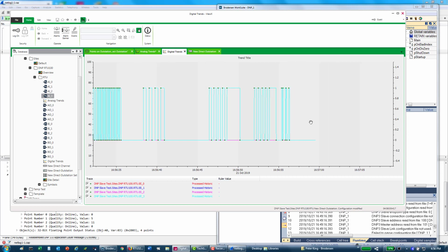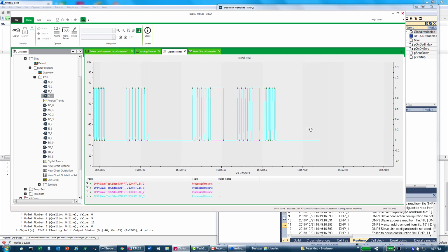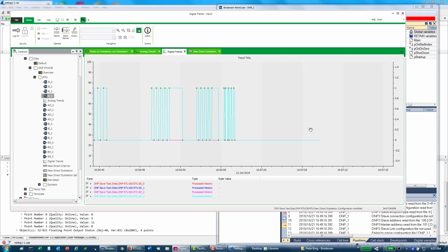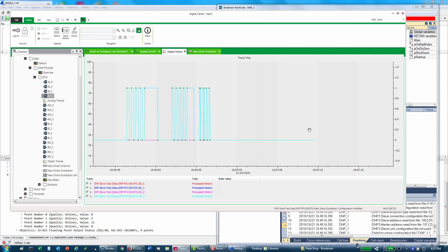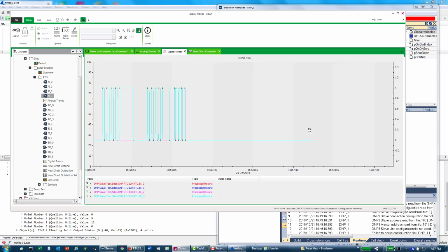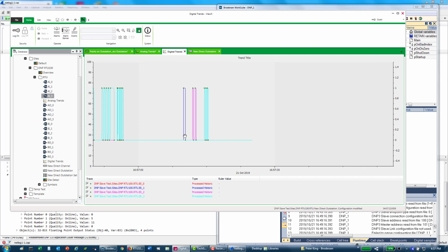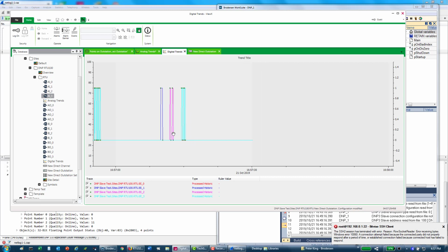And if I was to pull out the communications link to my RTU, so I've disconnected, I'm now making 1 Class 1 event, 2 lots of Class 2 events, 3 lots of Class 3 events. So nothing came through. We're going to plug back in, and ClearSCADA has now called this RTU once it re-established a connection, and I got back my 1 Class 1, my 2 Class 2s, and my 3 Class 3s. So we also proved that we could recover from a comms failure.